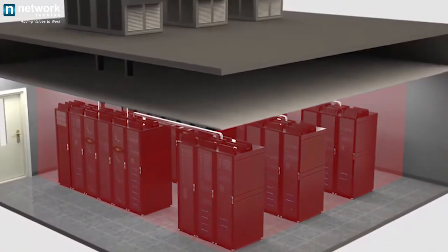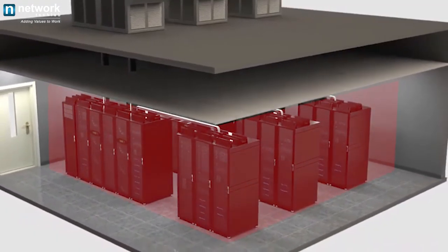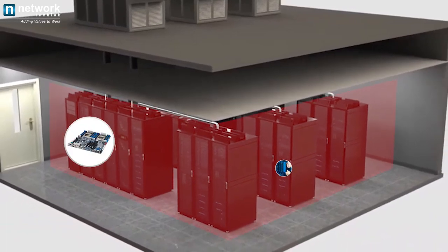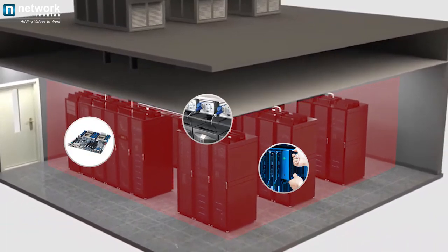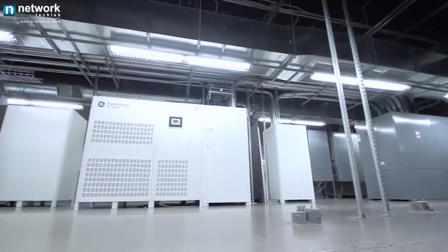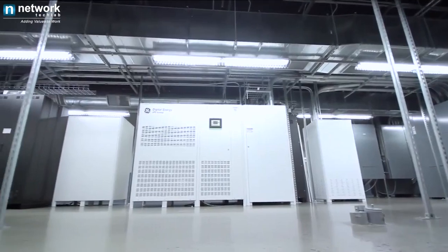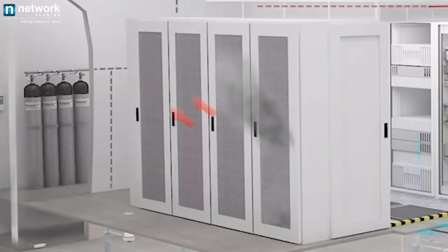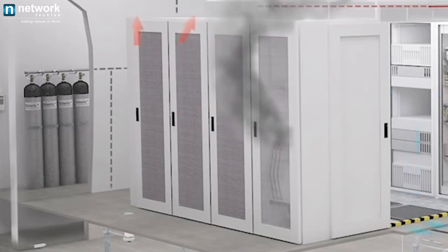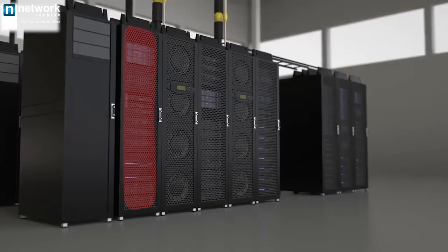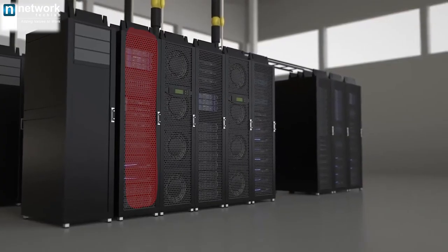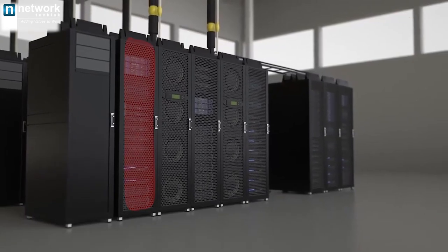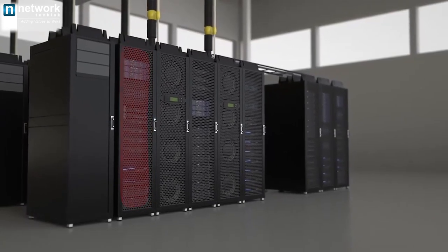Increased humidity in a data center results in the formation of moisture on motherboards, hard drives, and connecting sockets, which will quickly lead to corrosion and eventually equipment failure. The presence of harmonics in the power supply is a root cause of power quality problems and can result in increased heating of equipment and increased electricity costs. Hot spots could be a sign of an overheating electrical element, which could cause damage to other IT equipment.